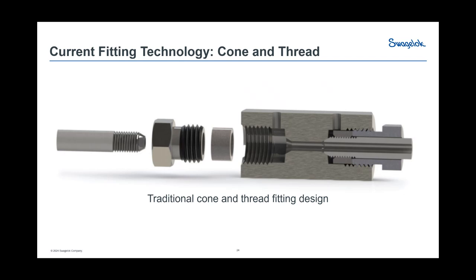So what we've seen in places where these things are out there is that they leak for a while. They go in to depressurize the system, go in to check it, and it reseals itself. The reason is that the side load has been taken off, or whatever was there, however it was there from when the system was running.